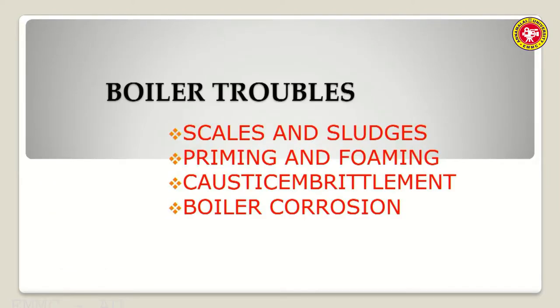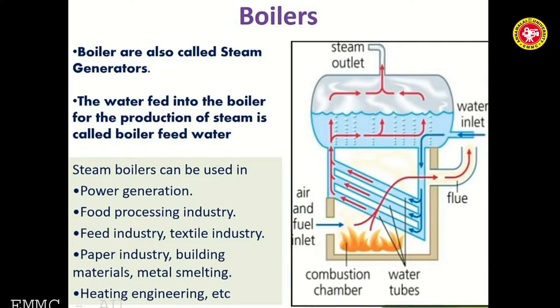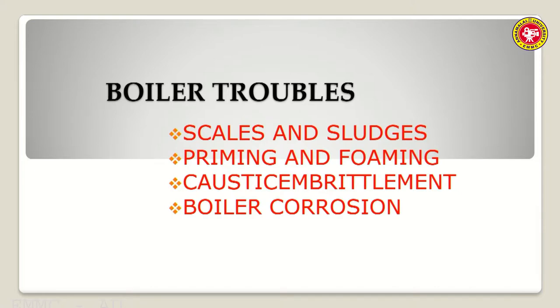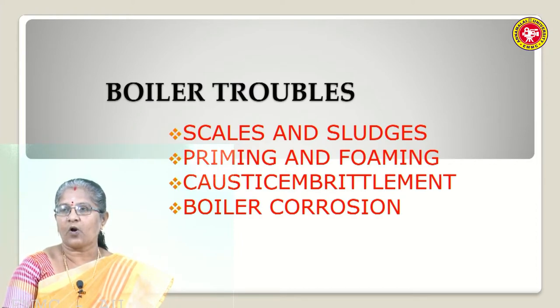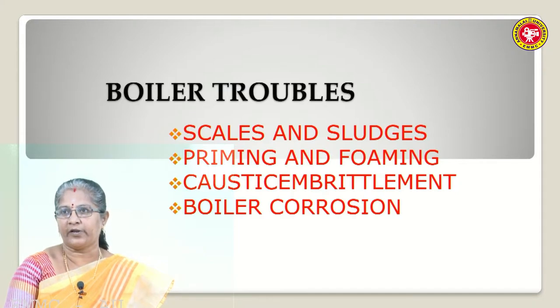These problems are called boiler troubles. Boilers use liters and liters of water; when boiled, steam is produced and used for power generation, food processing, textile industries, paper industry, etc. When hard water is continuously used in a boiler for steam generation, the salts deposit on the inner surface and cause many troubles. The four main boiler troubles are: formation of scales and sludges, priming and foaming, caustic embrittlement, and boiler corrosion.